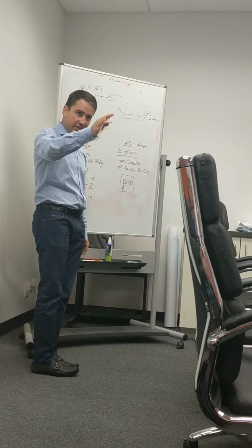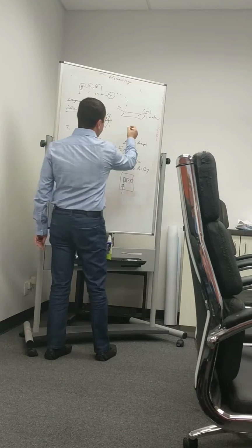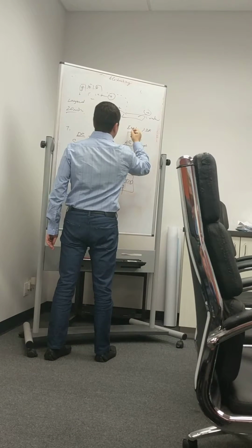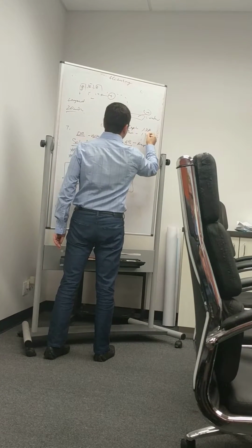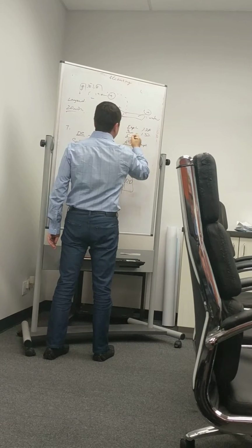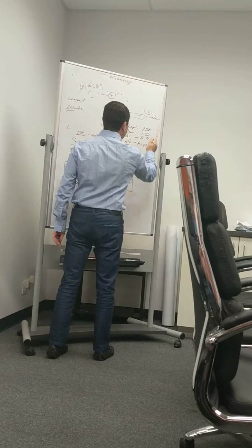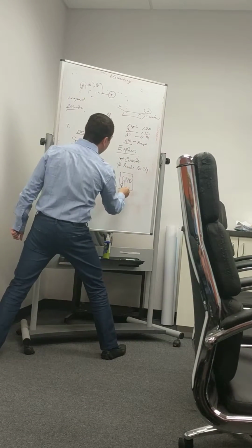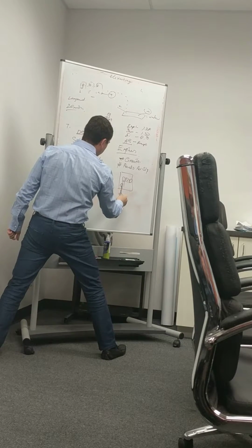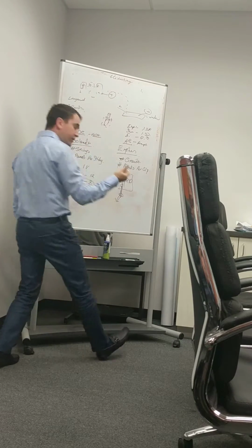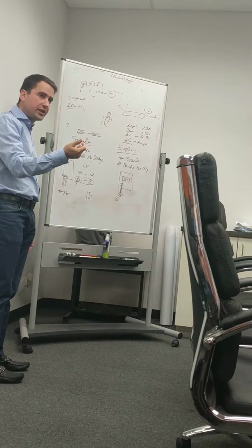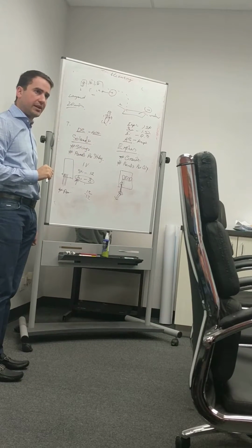About 1 amp, same thing. Enphase is about 1.20. SunPower is about 1.30. Enphase, the older model 0.90. So basically 1 amp. So if you put your clamp meter, and you measure the amps, you can see which branch circuit is good and which branch circuit is bad.